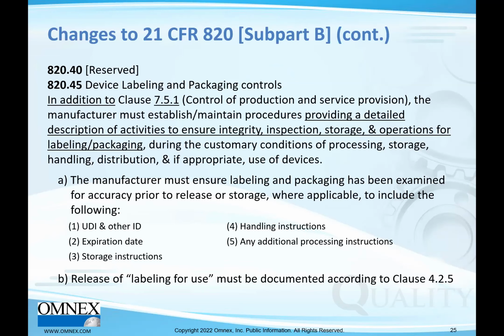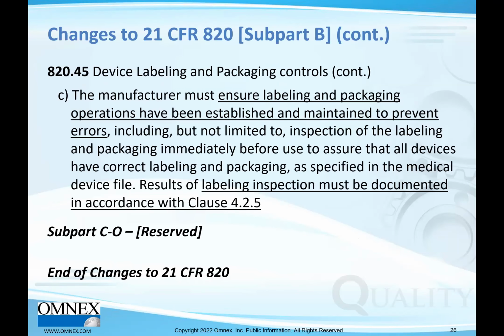Subparagraph B, release of labeling for use must be documented according to clause 4.2.5, which is control of records, again. Subparagraph C, the manufacturer must ensure labeling and packaging operations have been established and maintained to prevent errors, including but not limited to, a litany of items: inspection of the labeling and packaging immediately before use to ensure that all devices have correct labeling and packaging as specified in the medical device file. Results of label inspection must be documented in accordance with clause 4.2.5.